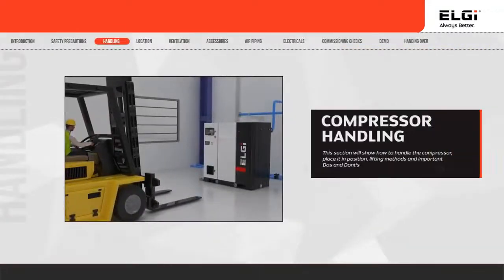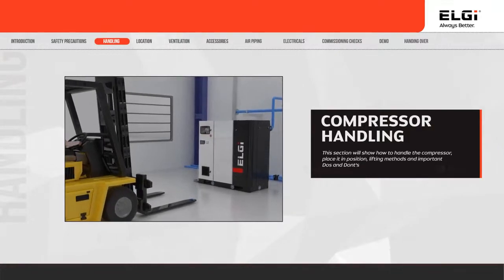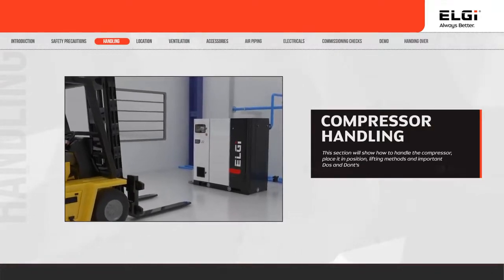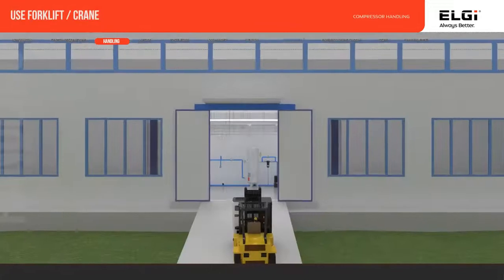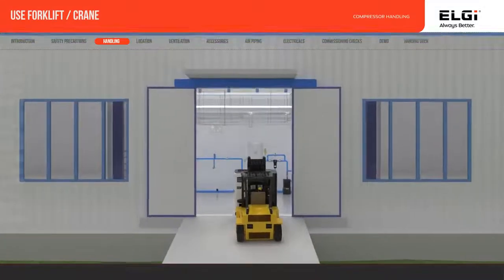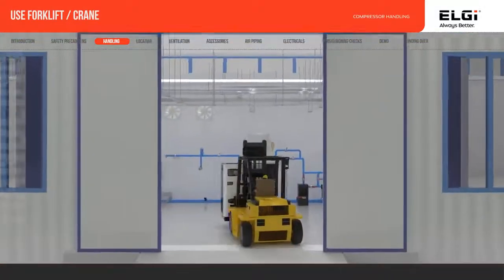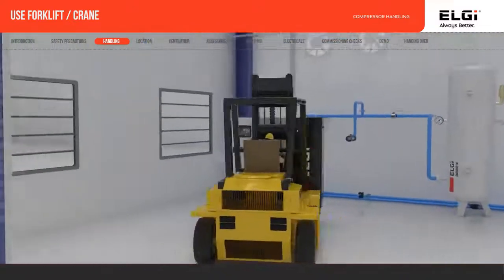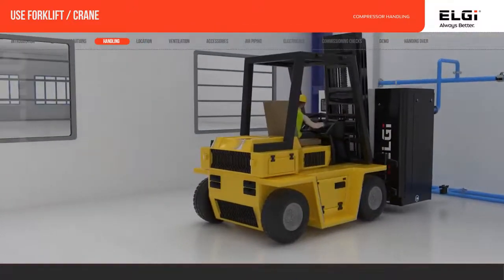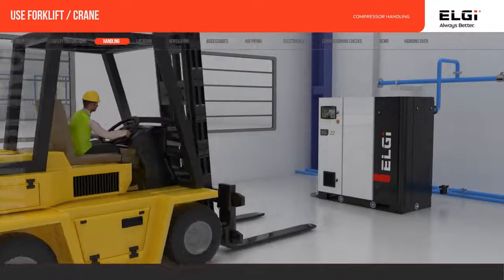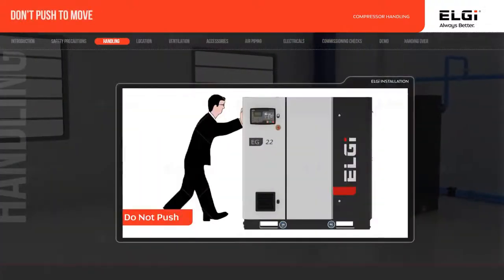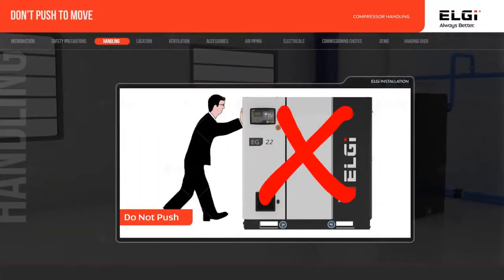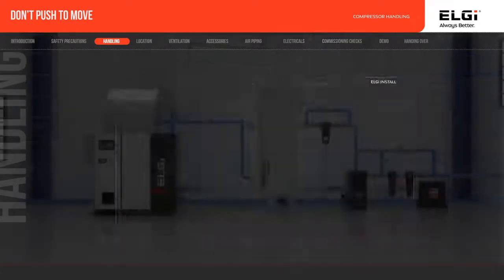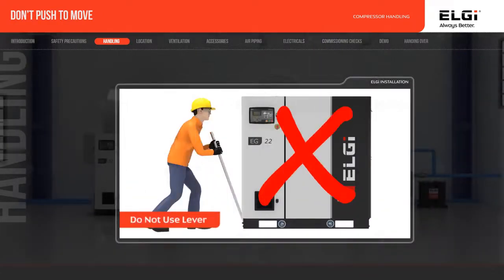It is very important that the compressor be handled carefully while moving it to its location and placed gently. Lift the compressor using a forklift or a crane. While placing the compressor, do not attempt to move it by pushing it, as this may cause jerky movements, damaging it. Don't use any hard lever to move the compressor.